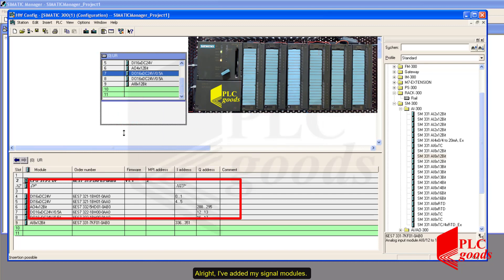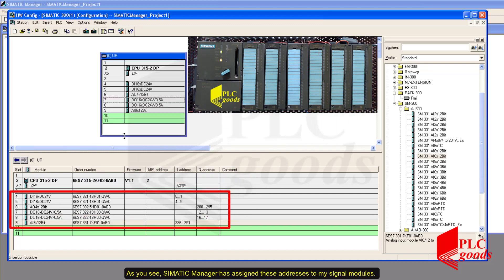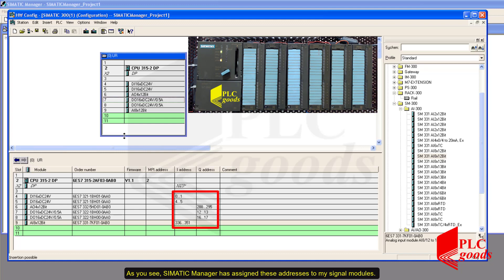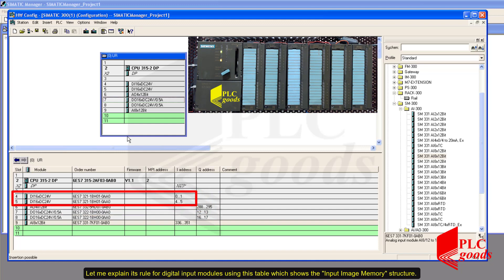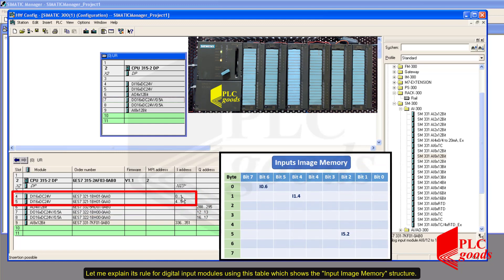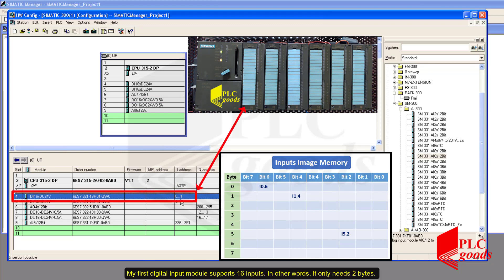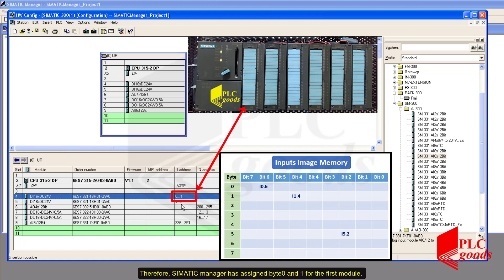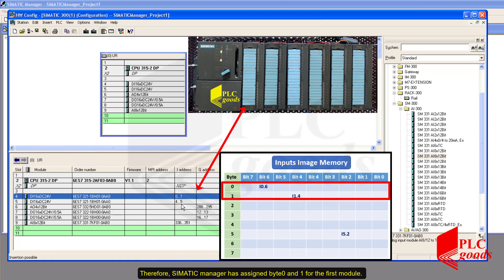I added my signal modules. As you see, Simatic Manager has assigned addresses to my signal modules. Let me explain the rule. For digital input modules, using the input image memory structure table, my first digital input module supports 16 inputs — in other words, it only needs two bytes. Therefore, Simatic Manager has assigned bytes 0 and 1 for the first module.